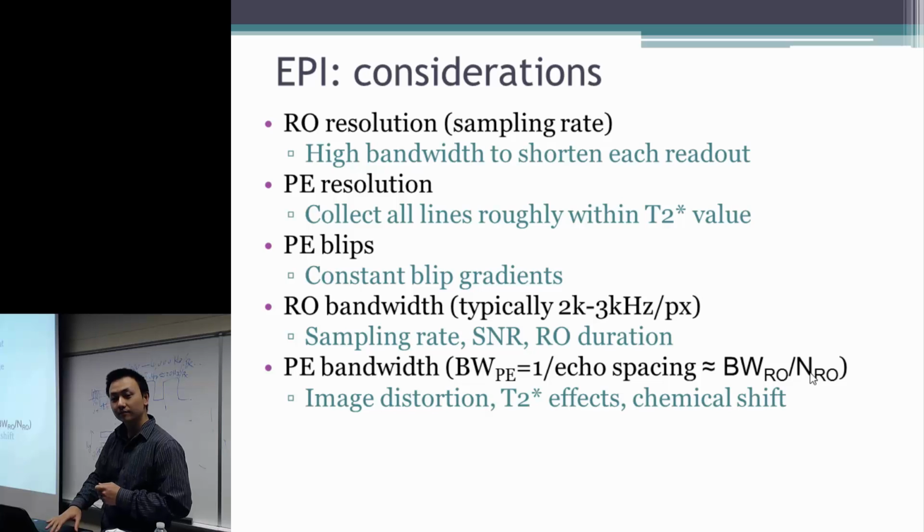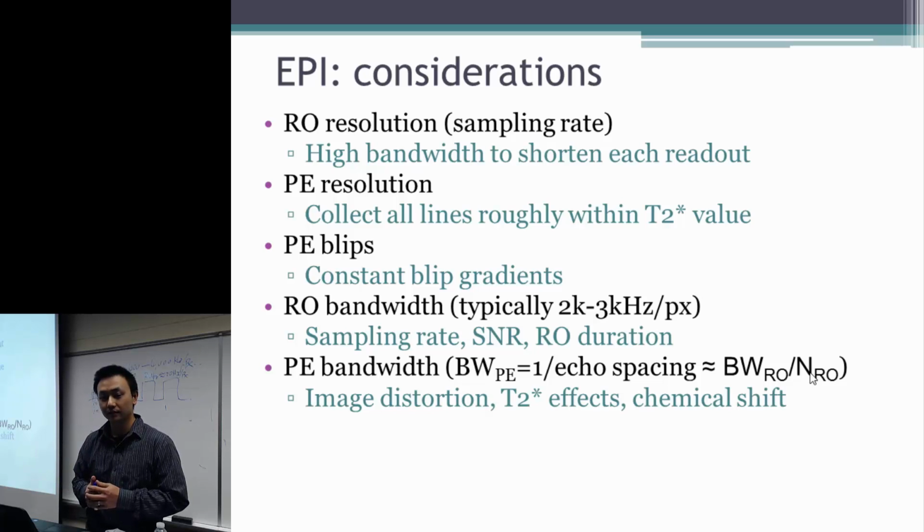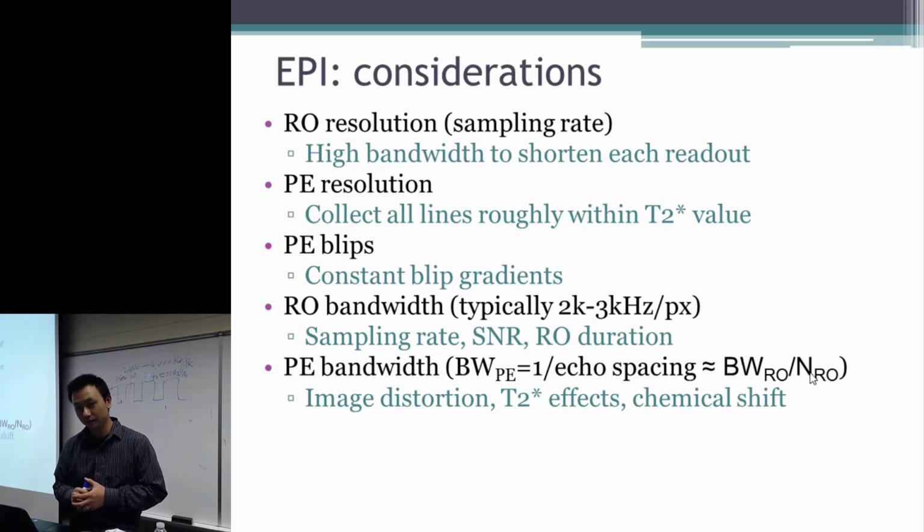So if the distortion is worse in the phase encoding direction, we should change it to the frequency encoding, right? If in EPI we have severe distortion in the phase encoding, that's because of the very low bandwidth, right? That's right. So we can replace it with the frequency encoding direction, right? Yeah, but it's this.